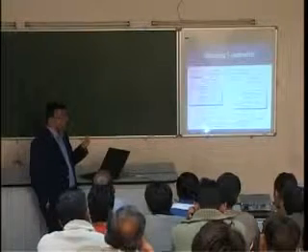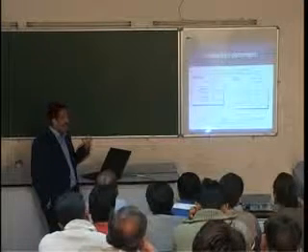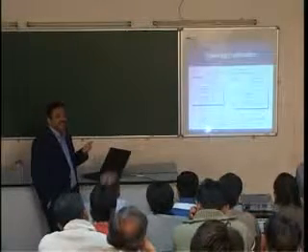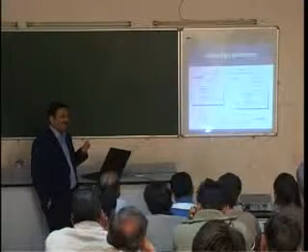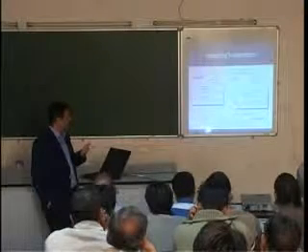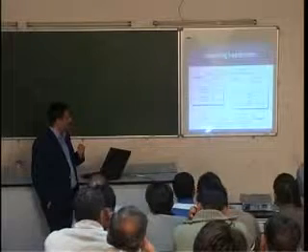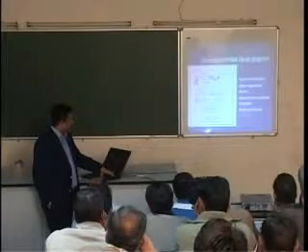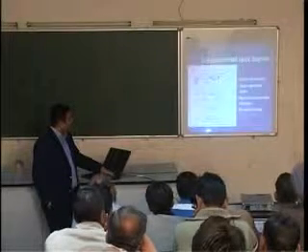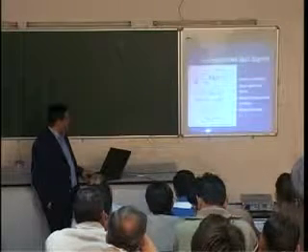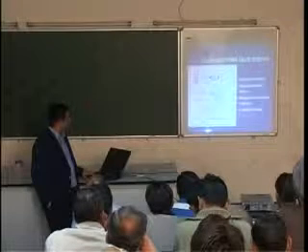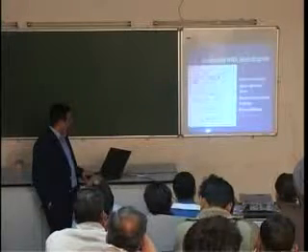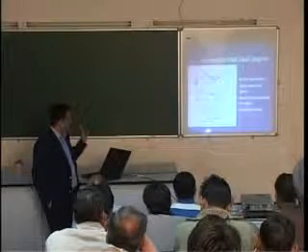And another thing is the directivity of the directional coupler, which is a very important parameter that ensures that the two ports where you are measuring the reflected and the incident signals are isolated from each other. So generally we say nearly 30 to 35 dB directivity is required for a directional coupler to ensure that we get a very accurate measurement, of the order of 0.1 dB, of the reflection coefficient. If that is not ensured, then there is a chance that we will get an erroneous measurement. This is basically how you configure your detectors, and these are two back-to-back directional couplers, and then you have the incident wave, and here you have a source, and you put tuned receivers or detectors here, and then you can get the ratio. This is a basic generalized network analyzer block diagram.